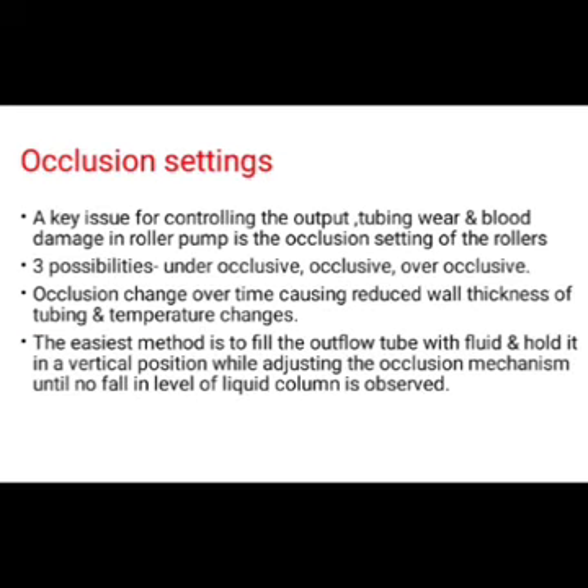Occlusion settings. A key issue for controlling the output, tubing wear, and blood damage in a roller pump is the occlusion setting of the rollers. Three possibilities: under occlusive, over occlusive, or occlusive. Occlusion changes over time, causing reduced wall thickness of tubing and temperature changes. The easiest method is to fill the outflow tube with fluid and hold it in a vertical position while adjusting the occlusion mechanism until no fall in the level of the liquid column is observed.